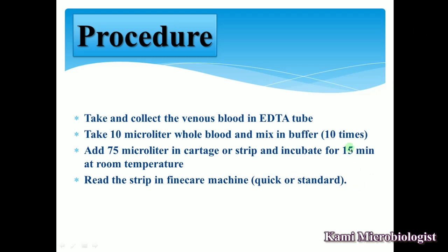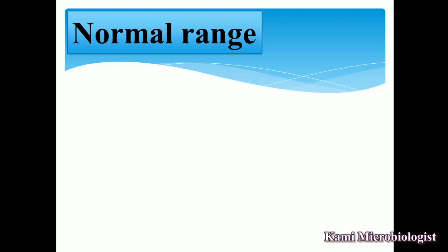Okay, I wrote 15 minutes, but in the Fine Care you just need 5-minute incubation, not 15 minutes. Once the 5 minutes is done, then you will run it quickly. If you didn't take the 5-minute incubation, then in the Fine Care machine you will just click on the standard machine. Let's see the normal range of the test.